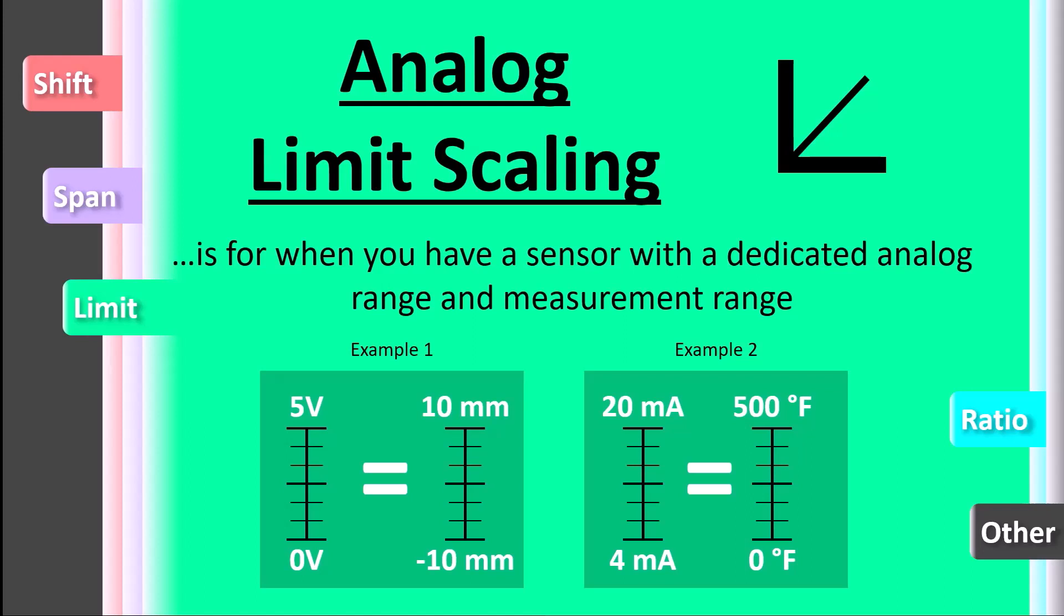Somewhere within the plus or minus 10 volt range is common for analog voltage outputs, and 4 to 20 milliamps is common for analog current outputs.